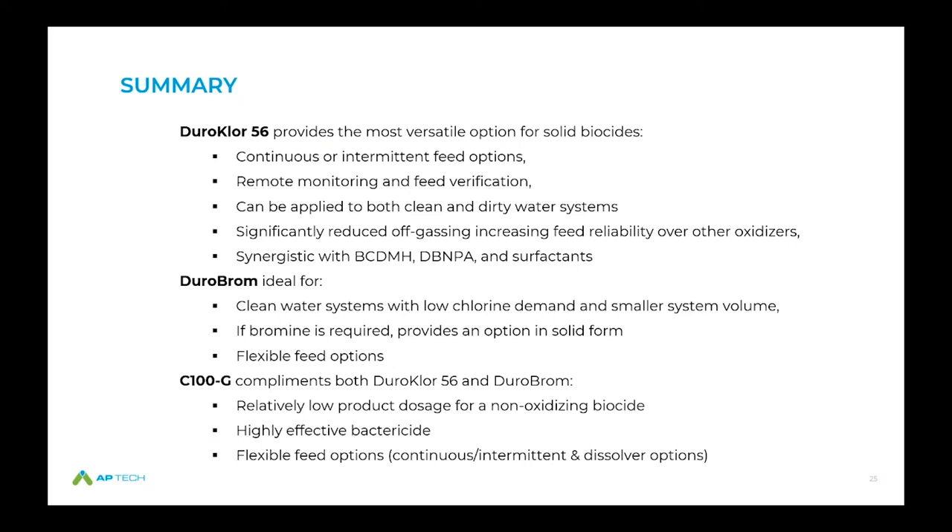DuroBrom is ideal for clean water systems with relatively low chlorine demands and smaller system volumes. It's synergistic with other biocides and surfactants, and if you need bromine, this is the option. You have flexible feed options and can do feed verification with ORP or halogen sensors. The C100G, whether used as a complement to oxidizers or as a standalone, is highly effective especially in cleaner water applications. It has a relatively low product dosage rate in the single digit ppm range and offers flexible feed options in terms of continuous or intermittent feed with available dissolver technologies.